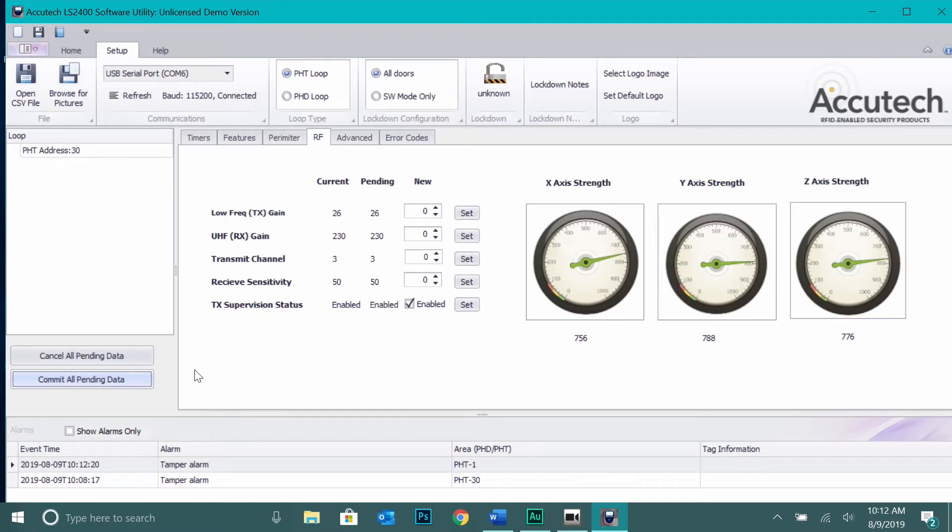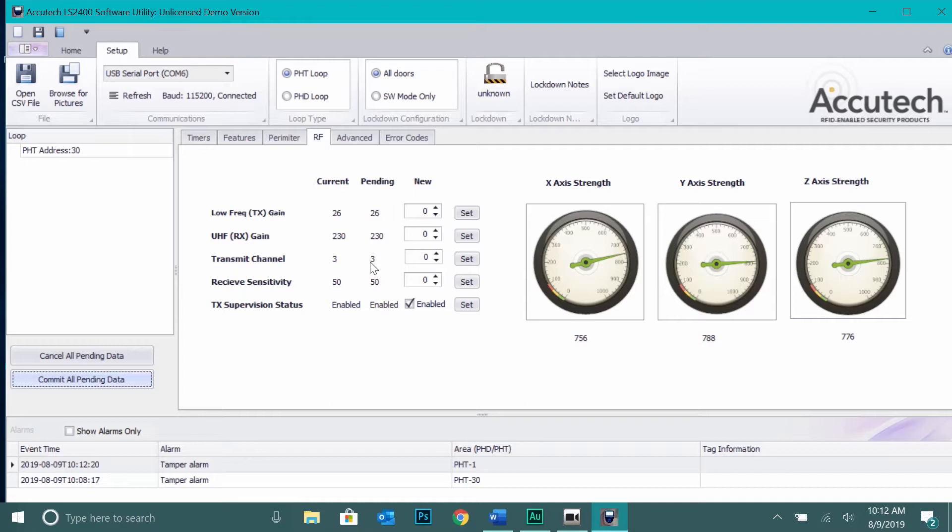Available transmit channels are values 1 through 9. Channel 3 is the default value for all door controllers. We recommend that if you are going to change frequency transmit channel to do this before tuning the door controller antennas to avoid a second retune after making changes.